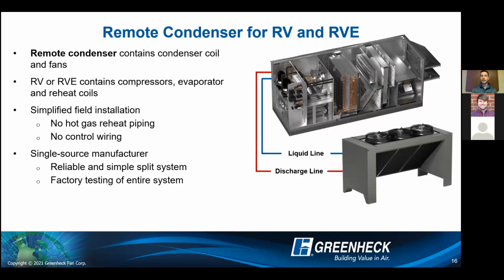And it also simplifies the field installation. So no hot gas reheat piping, no control wiring. All you really have to do is connect the liquid line and the discharge line once you get on site. You also get the single source manufacturer, which means it's a reliable and simple split system. We're able to support that product from a post-sale standpoint much easier. And you also get it factory tested. So it's going down the line together, both the actual unit as well as that remote condenser.